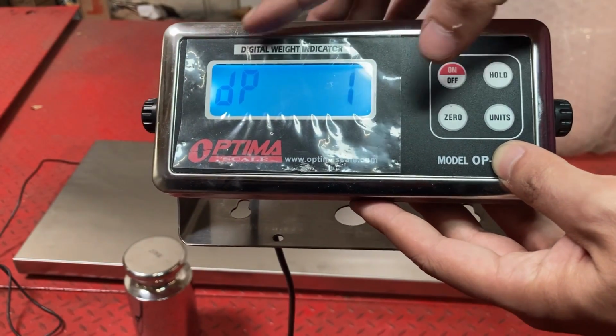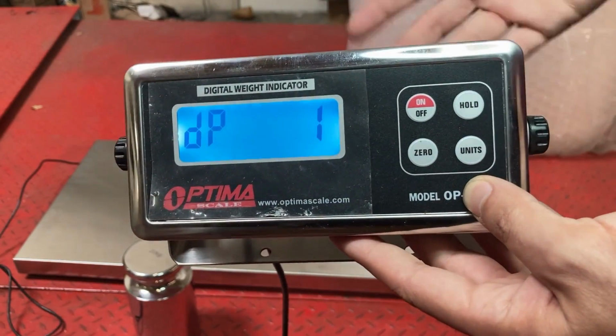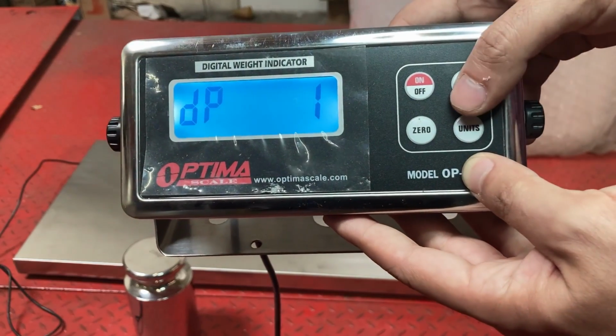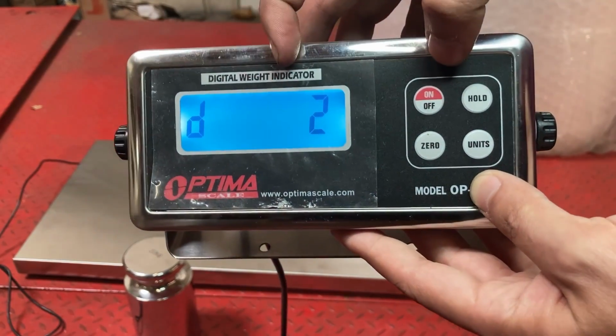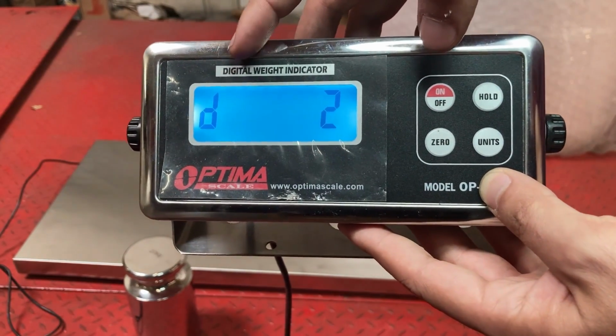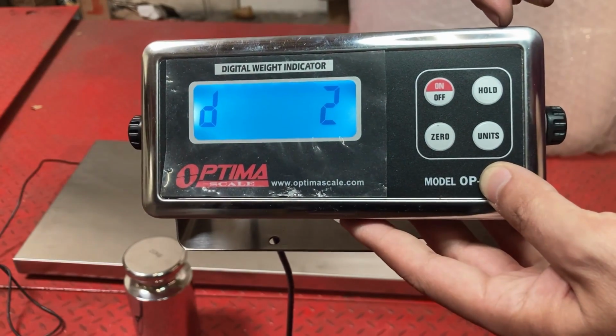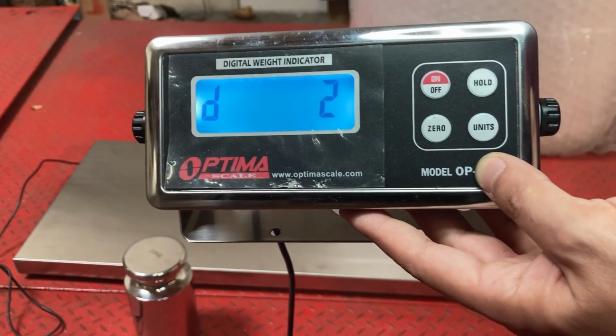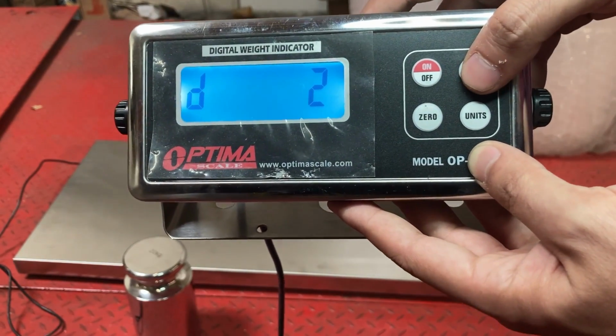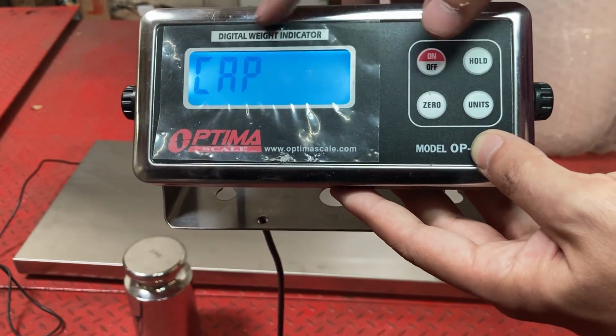DP, that's decimal places, set to 1. So yes, I want 1 decimal place, and vet scale is 1. And D2, that's just what it's counting by, incrementing by. I put 1 decimal previously, so it's not going to increment by 0.2 pounds, which is good. That's for vet scale. Cap, that's capacity.